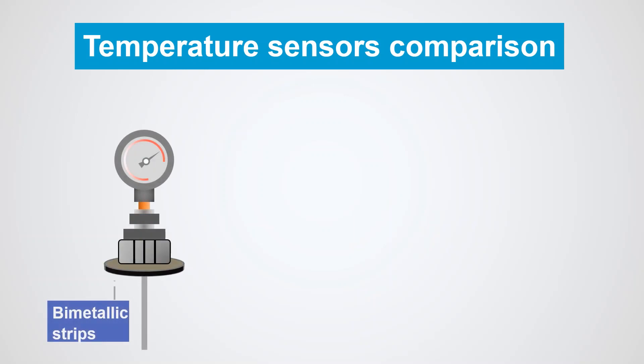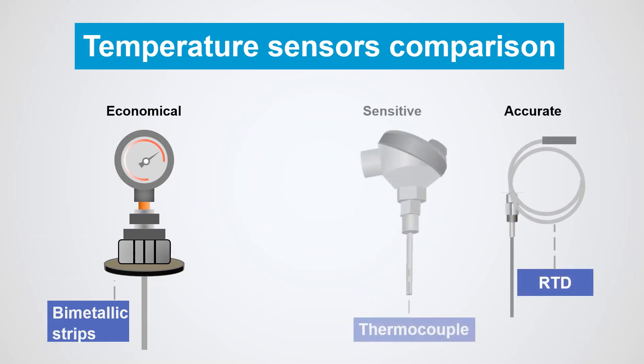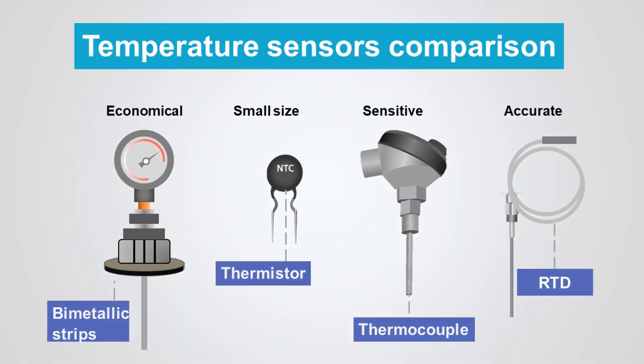Bimetallic strips are economical and can be selected for low-cost projects. If accuracy is required and is considered as the key performance indicator, usually RTDs are better than thermocouples, approximately 10 times more accurate. From the sensitivity point of view, while both RTDs and thermocouples respond quickly to temperature changes, at similar costs, thermocouples are often faster. Thermistors can be selected if temperature measurement is to be carried out in a small space.